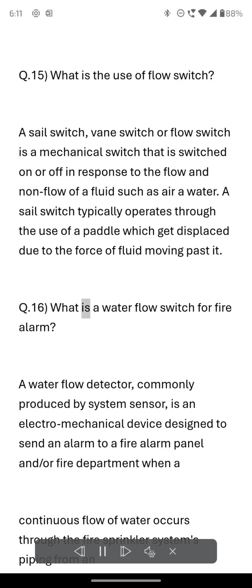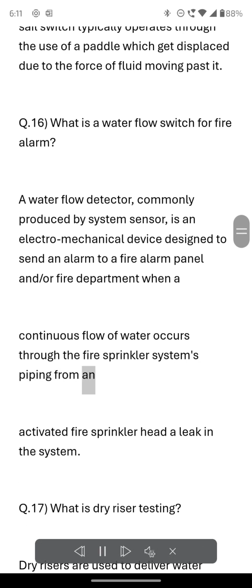Q.16. What is a water flow switch for a fire alarm? A water flow detector, commonly produced by System Sensor, is an electromechanical device designed to send an alarm to a fire alarm panel and/or fire department when a continuous flow of water occurs through the fire sprinkler system's piping from an activated fire sprinkler or a leak in the system.